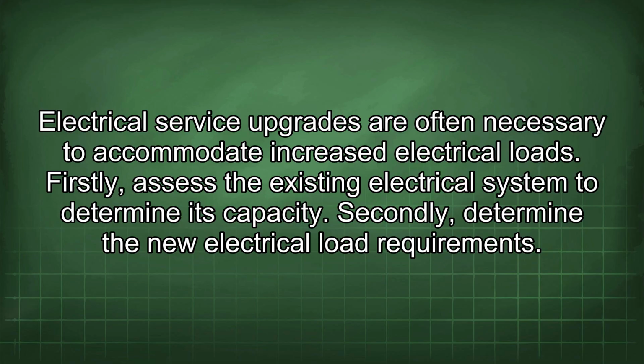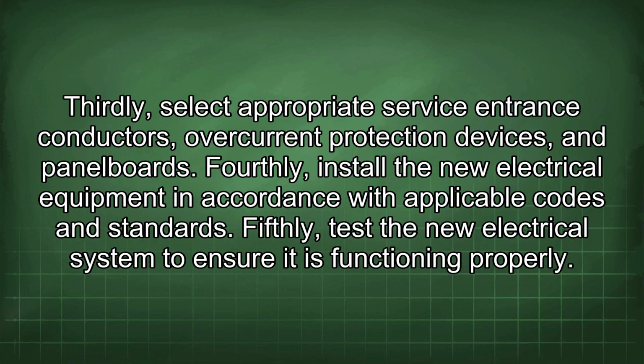Electrical service upgrades are often necessary to accommodate increased electrical loads. Firstly, assess the existing electrical system to determine its capacity. Secondly, determine the new electrical load requirements. Thirdly, select appropriate service entrance conductors, overcurrent protection devices, and panel boards. Fourthly, install the new electrical equipment in accordance with applicable codes and standards. Fifthly, test the new electrical system to ensure it is functioning properly.